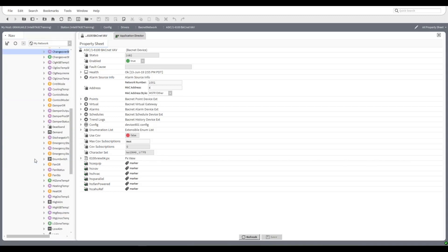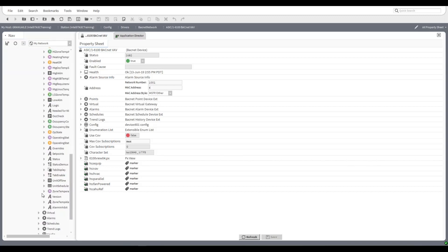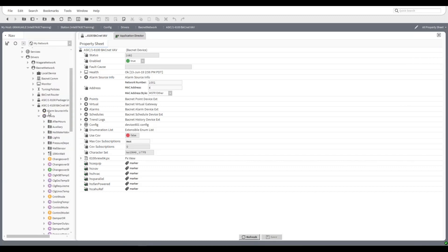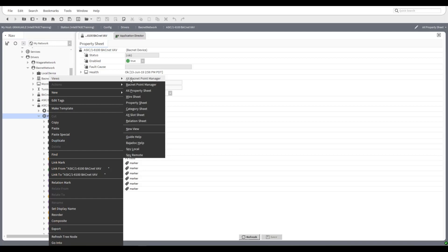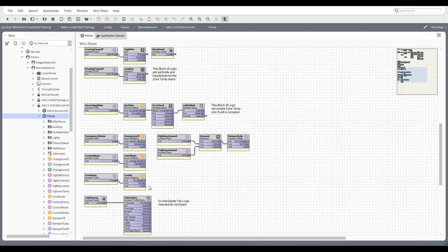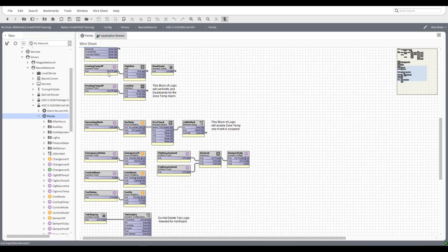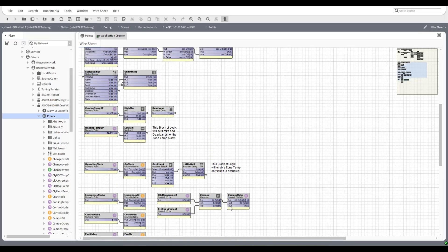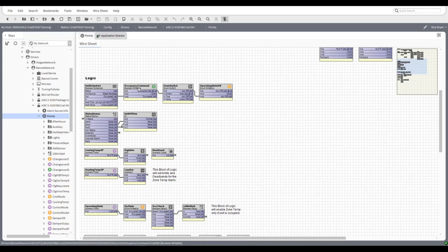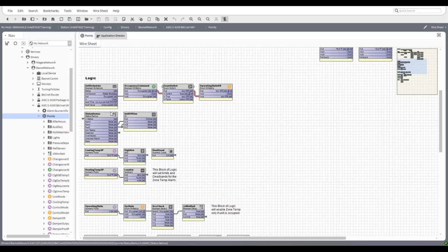Additionally with some of the points like zone temperature, you're going to get a history that you can use as well as an alarm extension for alarming high and low zone temperatures. In the wire sheet we have some logic as well that would be useful to you. The alarming is down here as you can see, with the cooling set points and heating set points generating the high and low alarm limits. At the top we have the ability to attach a schedule. There's a default schedule in there but if you want to use a remote schedule you can tie in at the binary level using this proxy or alternatively you can do an enumeration and tie in at this level as well. So you have options in terms of how you schedule this device and it's all there for you to pick and choose and modify as you need.